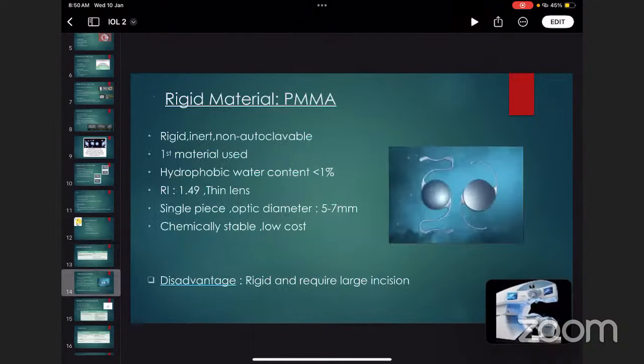Rigid material, polymethyl methacrylate, is a rigid, inert, non-autoclavable material. It was the first material used. It is hydrophobic in nature with water content less than 1%, refractive index 1.49. It's a thin lens, single piece, with optic diameter 5 to 7 mm. Chemically stable and low cost. Disadvantage: rigid and requires large incision to insert in the eye.